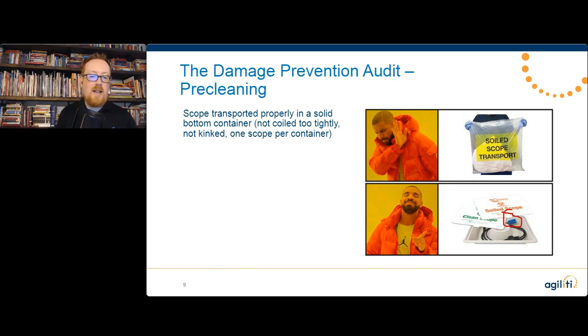But what they have done is they have taken their pre-cleaning sponge, and after they wipe that distal tip down, they left that sponge on the distal tip. The reason for that is it just gives that distal tip, where that really expensive CCD camera is, a little extra cushioning so that if it ever gets bumped into or banged against something, it's a little bit more protected than it was. Then you transport it to decontam with that, and in decontam they throw the sponge away. So it's just a little extra cushion, a little extra protection for that distal tip where all the money is. And I think that's a pretty clever and neat idea.